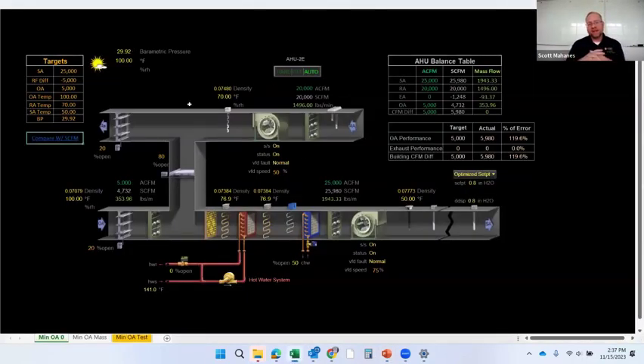I want to go through a simulation real quick on airflow control, because you can get the calibration on the flow sensors perfect, but the control of that airflow is still going to cause a little bit of a problem. And so for that, I'm going to go to this simulation. What I've done is track the air density of each of the supply air, return air, and outside air flow rates. And I can set these targeted values. What you need to focus on is that for the actual outside air, exhaust air, and building performance, there's a targeted value we're trying to achieve, and then there's an actual value we're going to end up having, and an error based on the actual differences that occur.